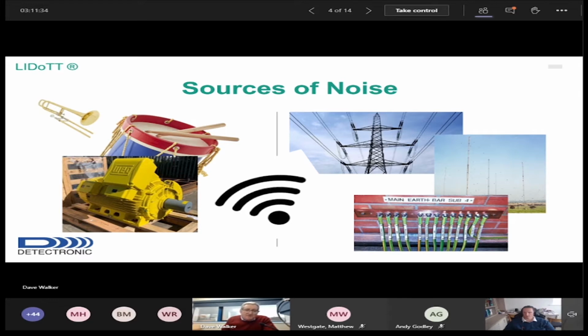The one on the left, motors and switchgear, can also give us big problems. When you've got high voltage switching, that can hit any power line and you just get a spike coming through. And the thing with instrumentation is we're dealing with very low signals, and then we amplify them up. An amplifier in its nature will amplify the signal. If you've got noise coming into the first stage of that 3-stage amplifier, then you're going to be amplifying the noise and not the true signal you want. So we've got to look at ways of eliminating that. And now EMC regulations work towards that, but are not foolproof by any means.